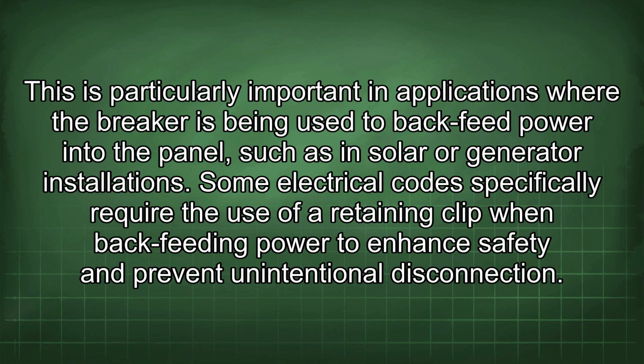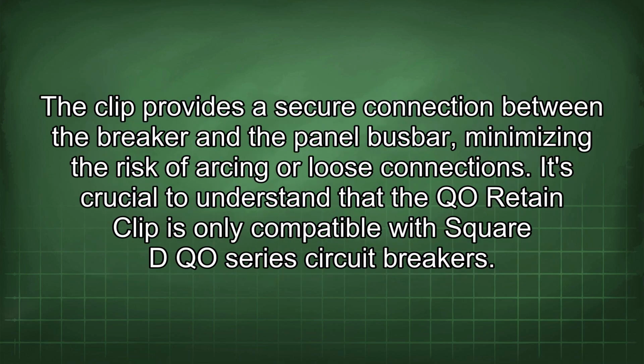Some electrical codes specifically require the use of a retaining clip when backfeeding power, to enhance safety and prevent unintentional disconnection. The clip provides a secure connection between the breaker and the panel busbar, minimizing the risk of arcing or loose connections.